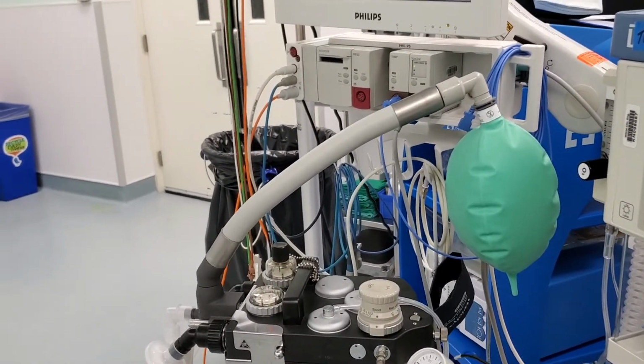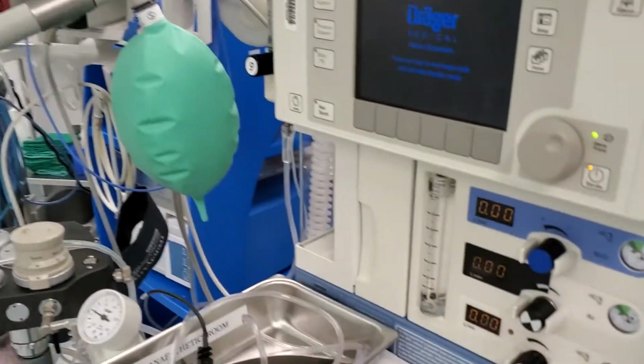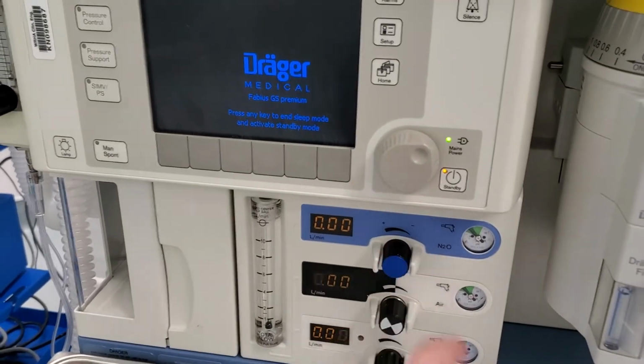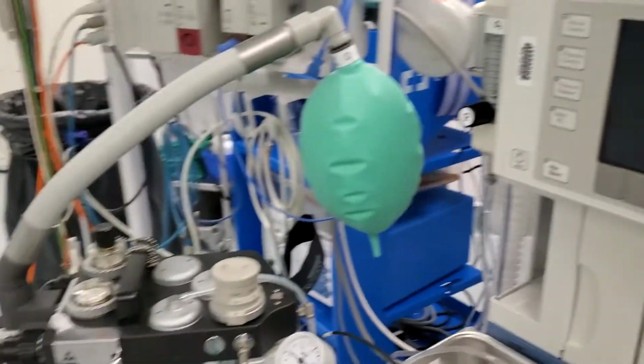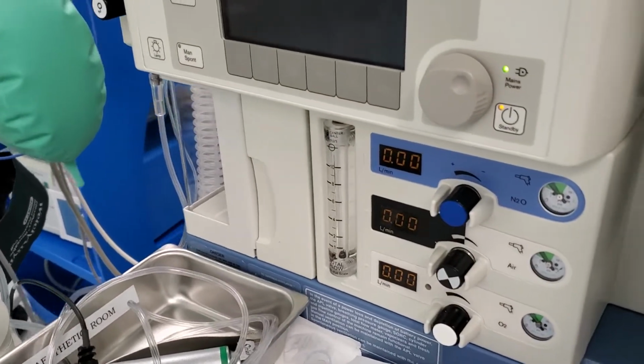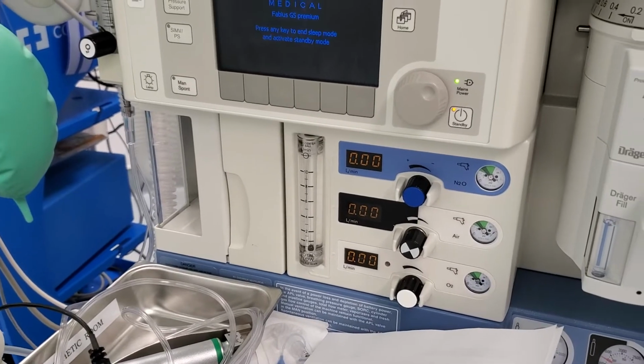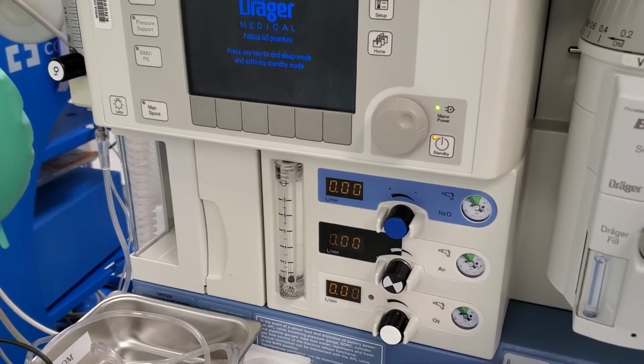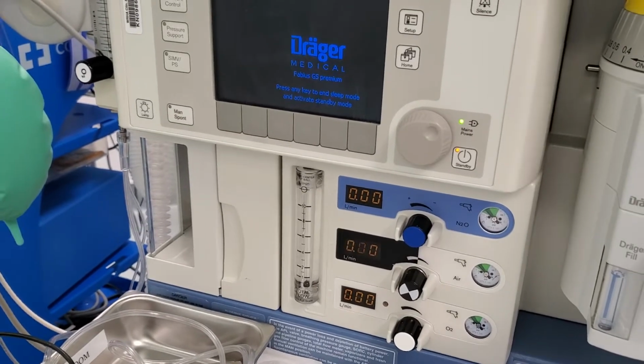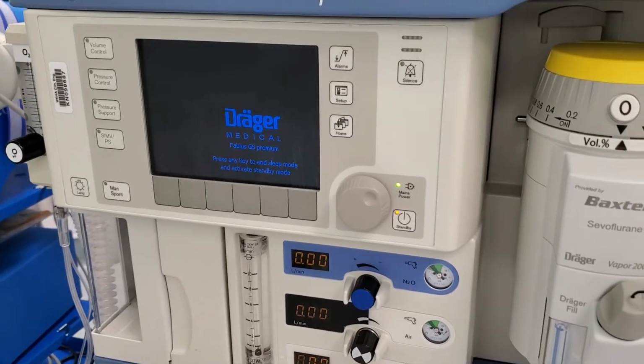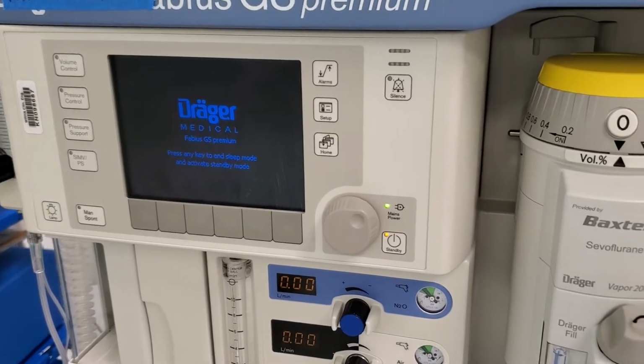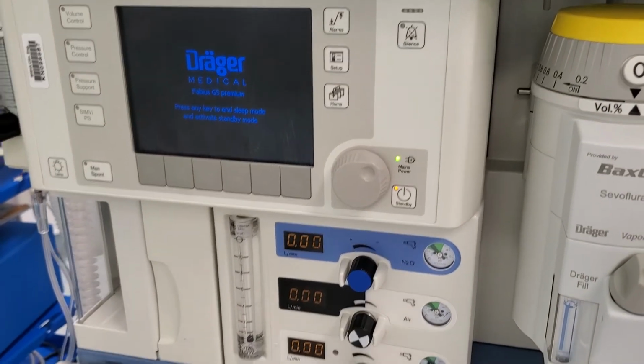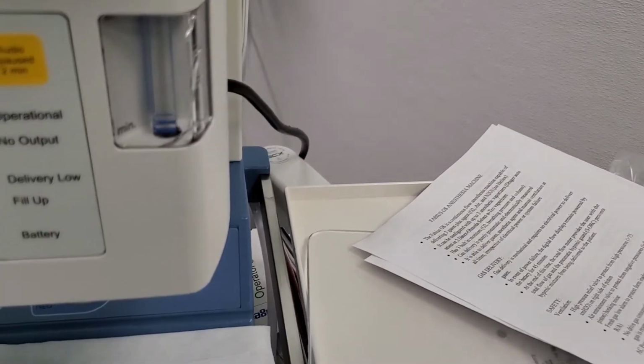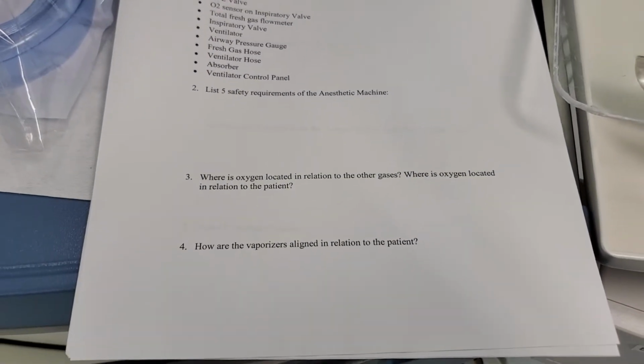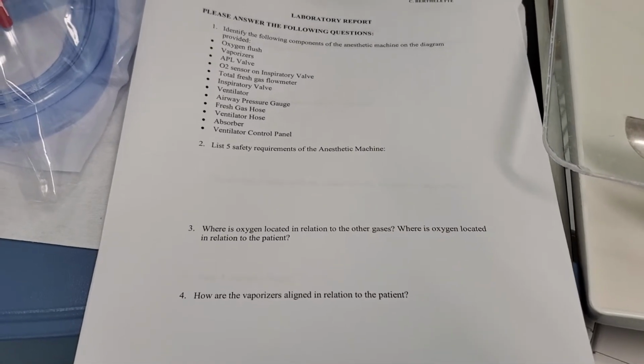So if we had oxygen, nitrous, and then the patient, we know that we can't set a hypoxic mixture because it won't allow me to turn up nitrous without oxygen. But say there was a leak that developed between the oxygen and the nitrous source, so our oxygen would be leaking out. The patient could then potentially get a hypoxic mixture. We would be able to keep an eye on that with our oxygen cell, but we need to keep a close eye on that. What else here? So oxygen is closest to the patient and downstream.